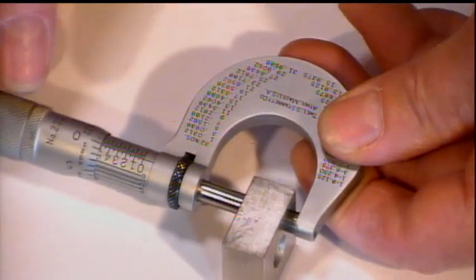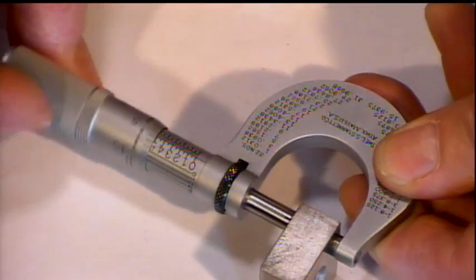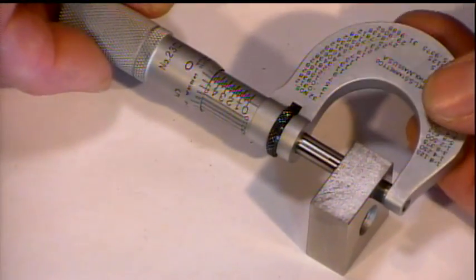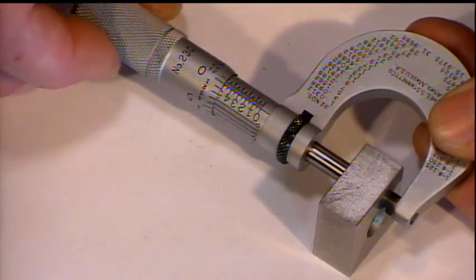But what we will do is we'll approach the measurement. As we get near, we'll either move the part slightly or we'll rock the micrometer slightly and really get it down to where it's touching and contacted. Maybe show that on the gauge cam a little bit closer. Yeah. Sure. To where everything is right there before we do the final turn. So again, we're a little loose, we're a little cockeyed, so we go in and we just keep going until everything is very, very smooth in contact. A lot of machines will do a final push and then do the reading. And now you'll see the reading is exact.